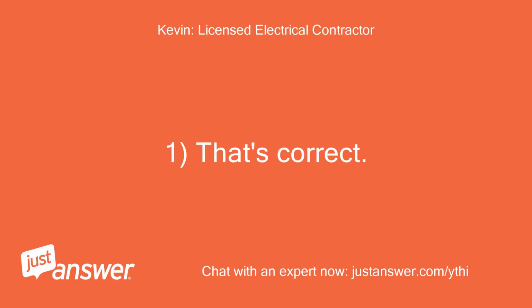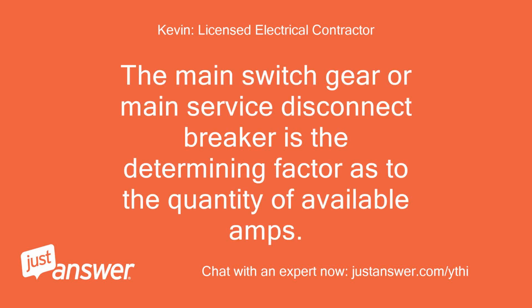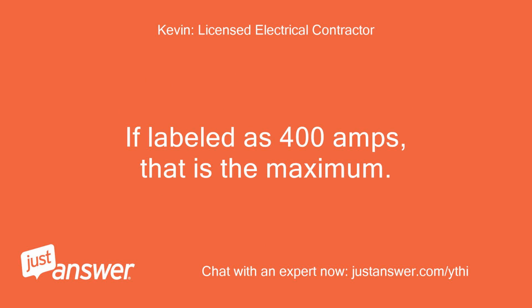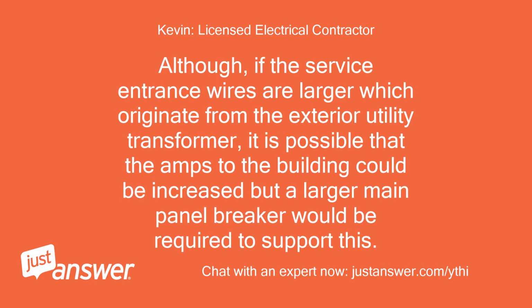1. That's correct. The main switch gear or main service disconnect breaker is the determining factor as to the quantity of available amps. If labeled as 400 amps, that is the maximum. Although, if the service entrance wires are larger which originate from the exterior utility transformer, it is possible that the amps to the building could be increased but a larger main panel breaker would be required to support this.